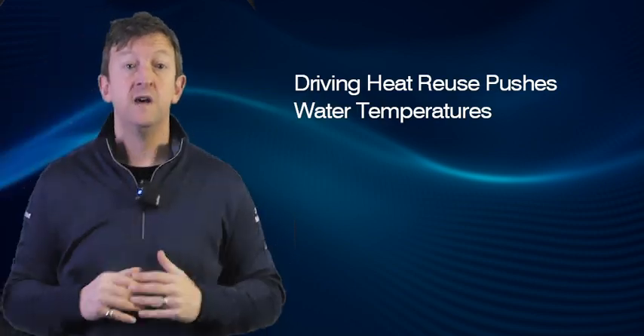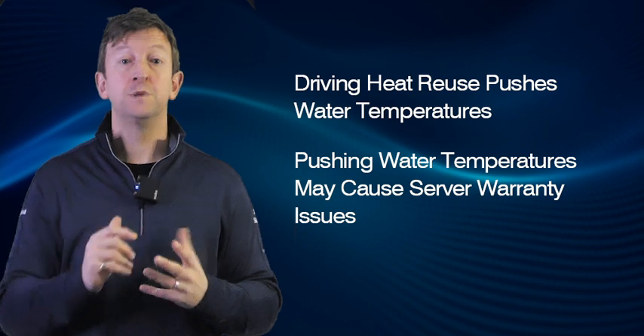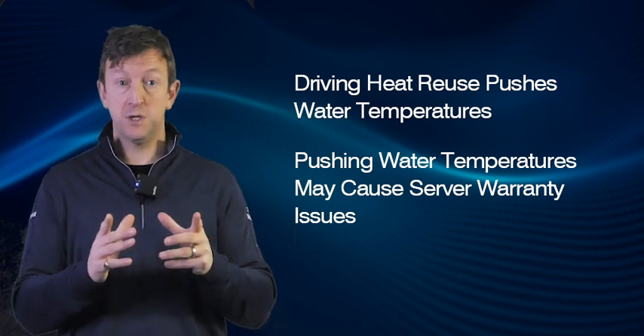There are marked opportunities for heat reuse via data center operators and liquid cooling. However, there can be a trade-off regarding sustainability and performance in liquid cooling. To drive heat reuse, you need to push your water temperatures up, and when pushing your temperature envelopes, you may run into server warranty issues.